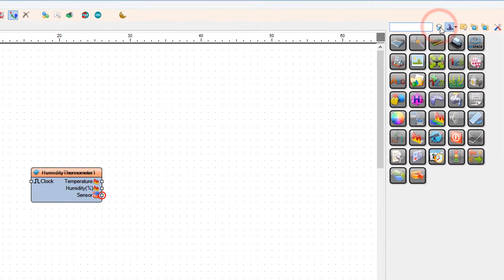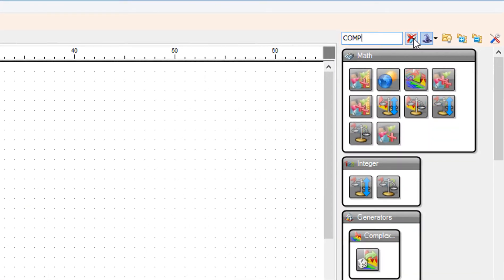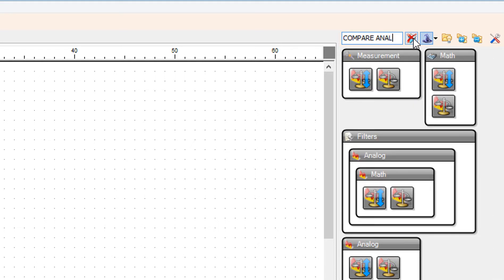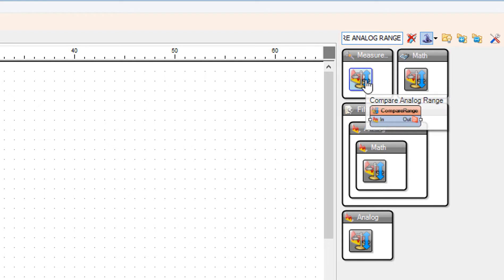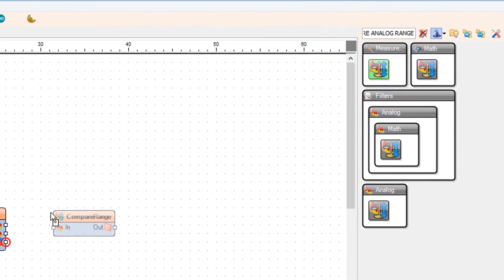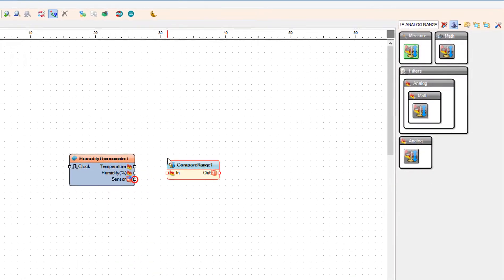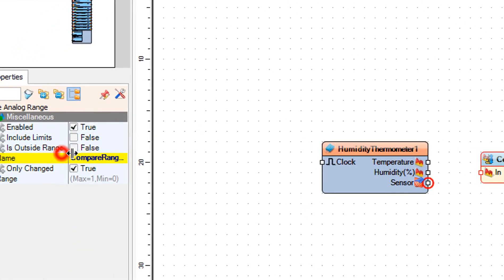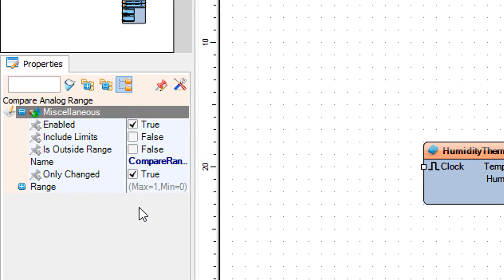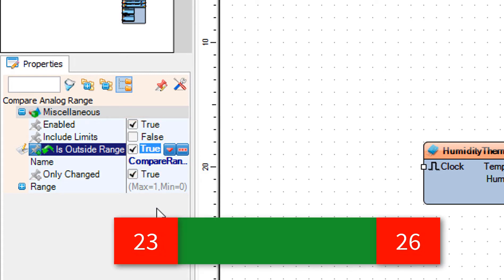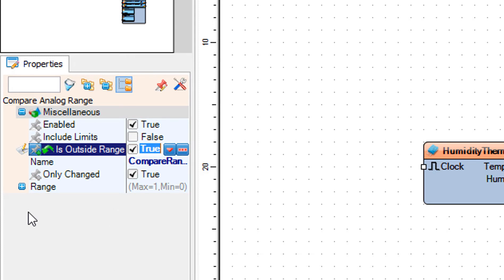Add compare analog range component. For this example we will use the temperature range 23 Celsius and 26 Celsius, but you can adjust the temperatures to your needs. Select compare range 1 and in the properties window set is outside range to true. This means that we want to measure and trigger the alarm if it's more than 26 Celsius or less than 23 Celsius. If you want to trigger the alarm just in the range between 23 to 26 Celsius, then set the is outside range to false.